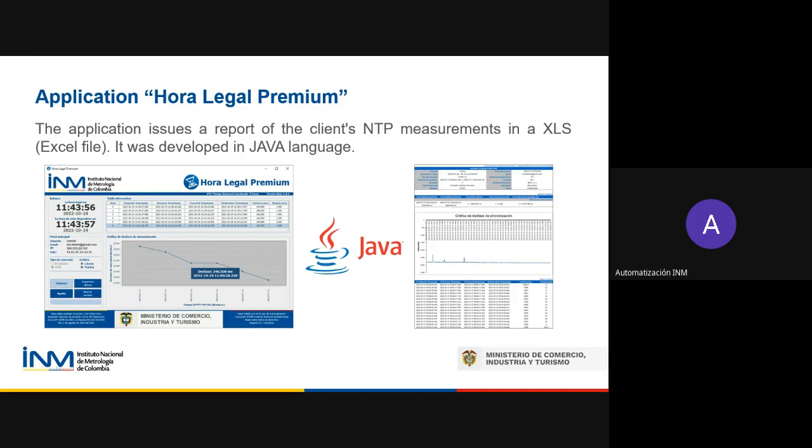It contains all data obtained from the measurements and a statistical summary showing values such as maximum, minimum, mean, coverage factor, and expanded uncertainty. This file is the main input to create the digital calibration certificate. The file must be entered by the user into the application that issues the DCC.